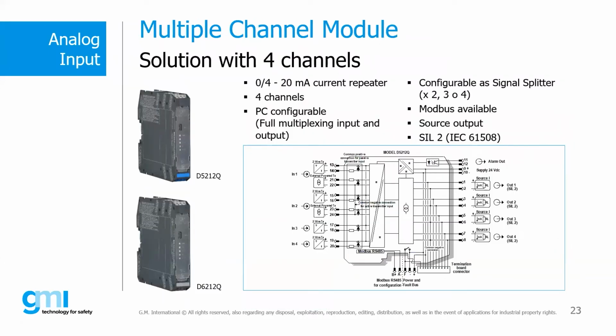We also have a solution with a 4-channel, multiple channel. So in this case, 4 to 20. Just to explain, in the slide you may see two pictures. One is for the intrinsically safe isolators with a blue label, and one is for the standard isolator, for non-IS application, the 6000 with a green label. So in almost all units we can have the double solution. In this case, we have a double solution for 4-channel with a 0, 4 to 20 milliamp current signal.